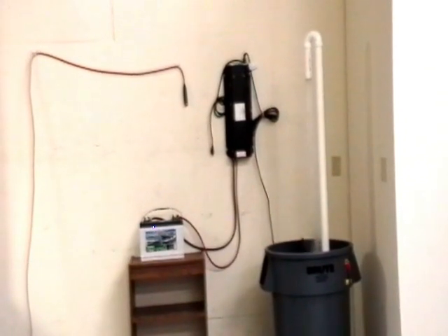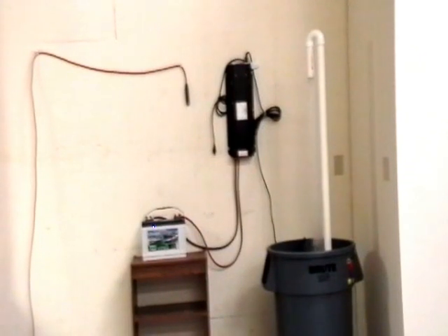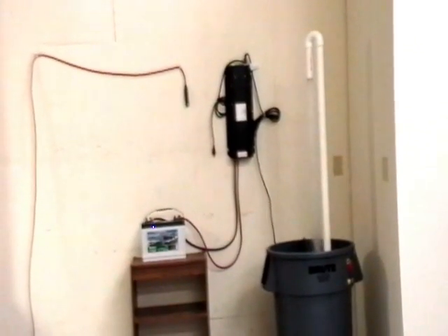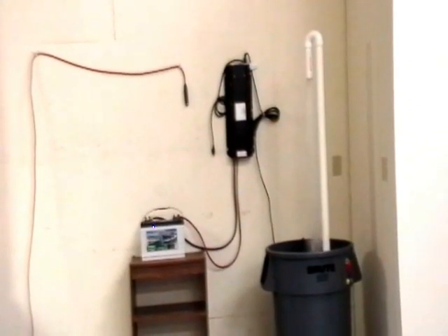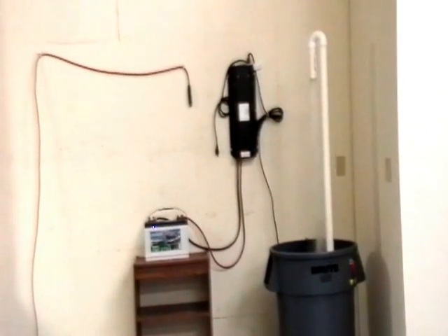There is no AC coming from anywhere except from within the 1612 pump sentry. I will now demonstrate the transition back to AC power by plugging the AC in, and you will notice that the pump resumes operating seamlessly.